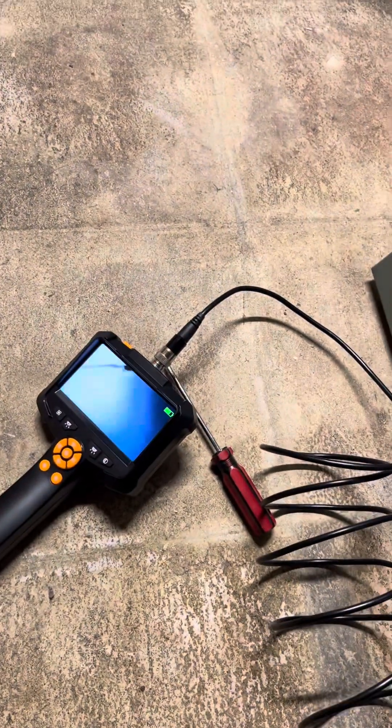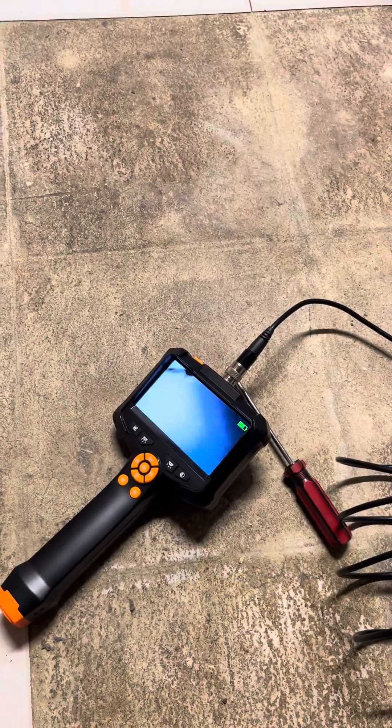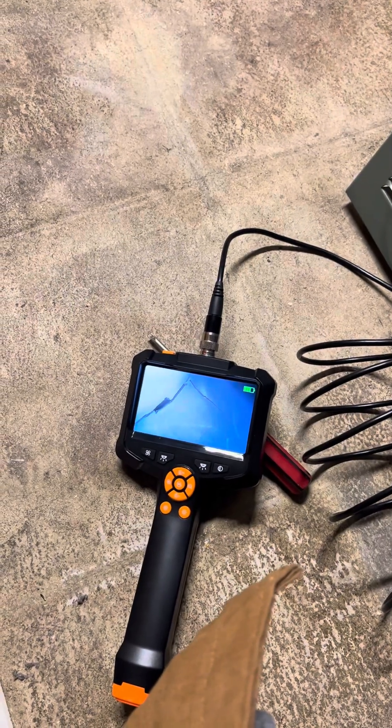None of the air from the tubes should mix with the air that blows through the vents. Flue gas contains carbon monoxide. It's all supposed to go up through the chimney. Now, if one of those tubes breaks, you've now opened the seal and introduced the flue gases into the air that blows through your vents.